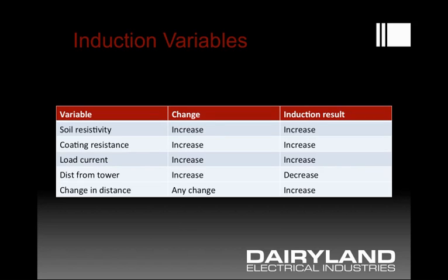Here's the relationship between induction and other factors. If soil resistivity increases, the induction on the pipe — all things equal — also increases; the soil along with the coating makes the pipe look more isolated from earth, like a better insulation system. If coating resistance increases, the same result happens — better coatings mean this is more of a problem. As load current on the power line increases, so does the magnetic coupling and induction on the pipe. With increasing distance from the tower, induction decreases, producing lower induction and also lower arc risks. However, if there is ever a change in distance from the pipeline to the power line, any change at all will result in increased induction at that point of change.